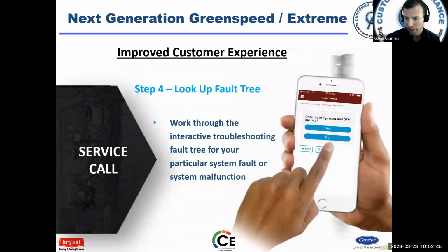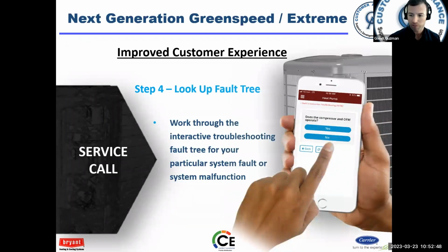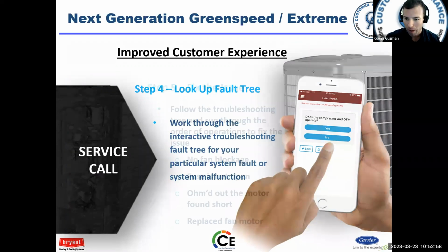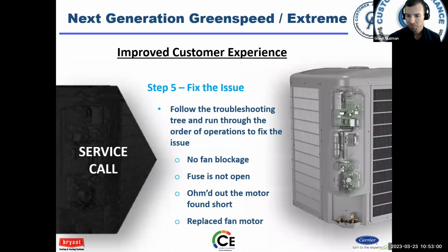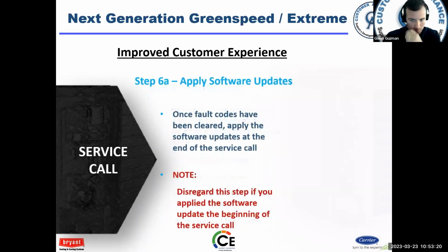Then you can go through the interactive troubleshooting tree to troubleshoot this and track down where the problem is. As you go through, look for fan blockage, check the fuse, ohm the motor. We ohm the motor out and find a short. It's a good thing we brought the fan with us, so I can change the fan motor out and be on my way, replace it, and get it going.